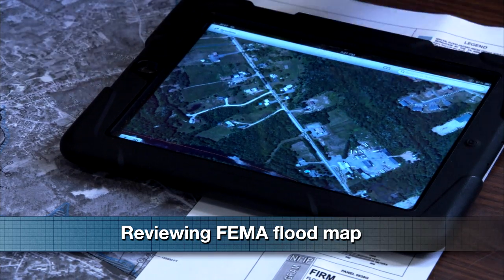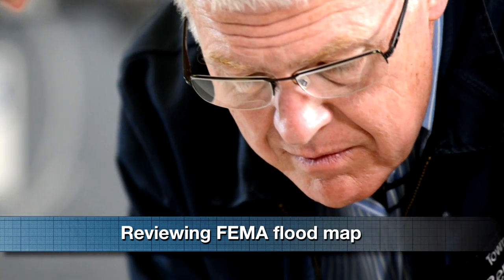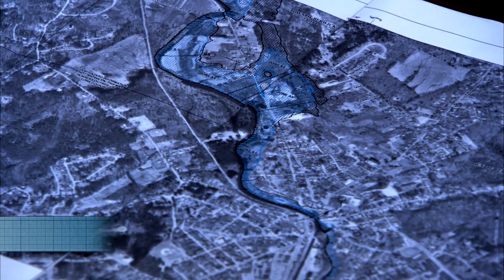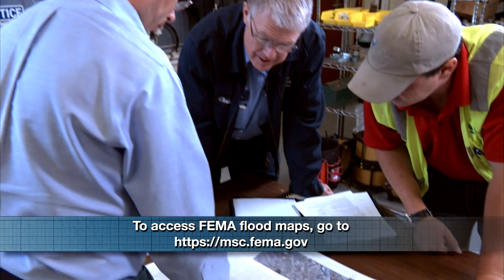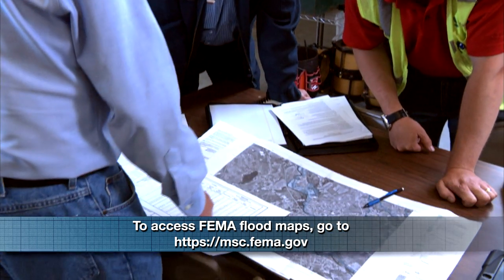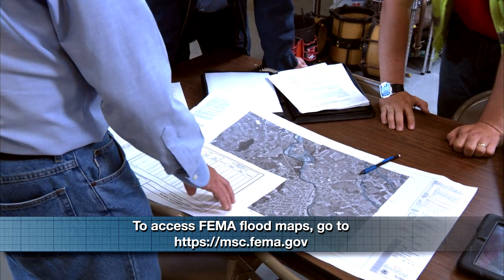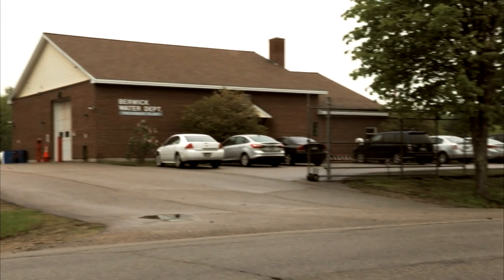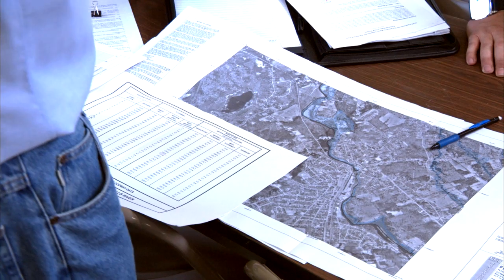We've got this showing that we are in the 500 and not in the 100, and then the 500 year is going to be another 3 feet higher than that. That's a lot. But that kind of makes sense in terms of the profile of knowing where you got in the driveway compared to where we were. So it's very possible that the floor of the facility will flood at a 500-year flood.